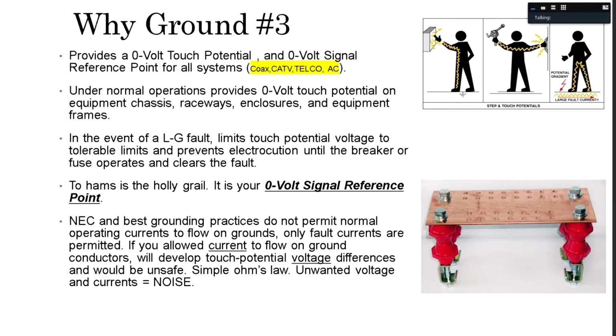And by everything, I mean coax, cable TV, telco, AC, any services coming to your home. Under normal operations, it provides your 0-volt touch potential on equipment chassis, raceways, enclosures, and equipment frames. If you were to have a line to ground fault, it's going to limit the touch voltage on the equipment chassis and prevent electrocution until either the fuse or the breaker operates to clear out the fault. But to hams it's kind of the holy grail because it is your 0-volt signal reference.